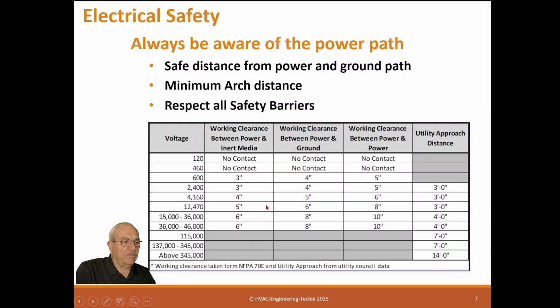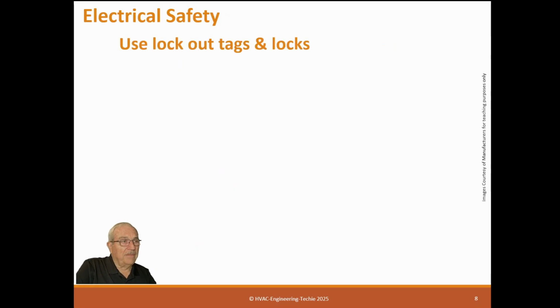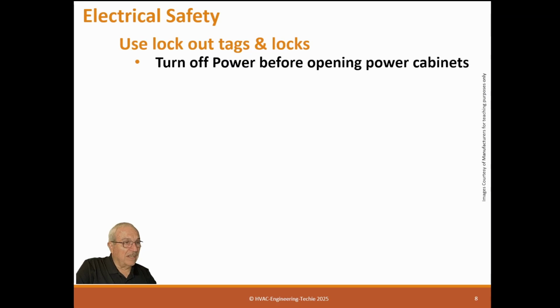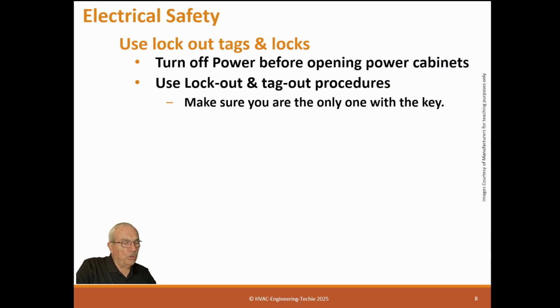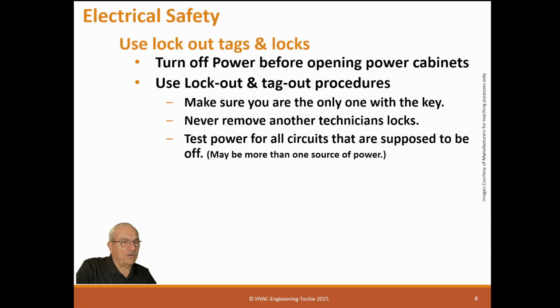And I don't know, but if you've ever worked on a 12,000 volt or 15,000 volt panel, when you hit a panel that's activated with 12,000 volts, the hairs will stand up on your arms. And you get a clue right away: I don't want to get closer to that. I'm close enough. So you want to be careful with that. Use lockout tags and locks. Turn off power before operating power cabinets. Use lockout and tag out procedures. Make sure you are the only one with a key to your lock. There can't be multiple keys. You've got to be the only one. Never remove another technician's locks. That's a no-no.